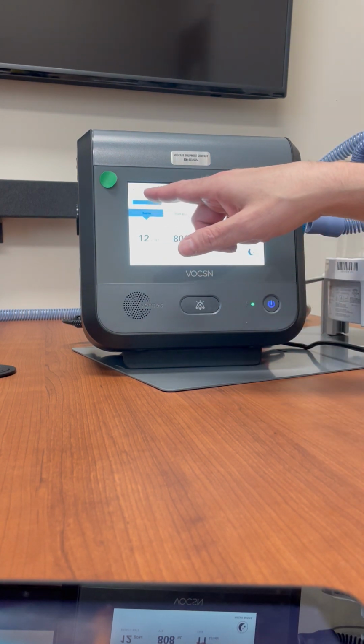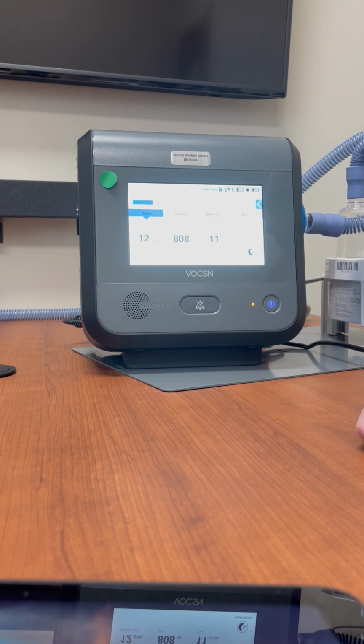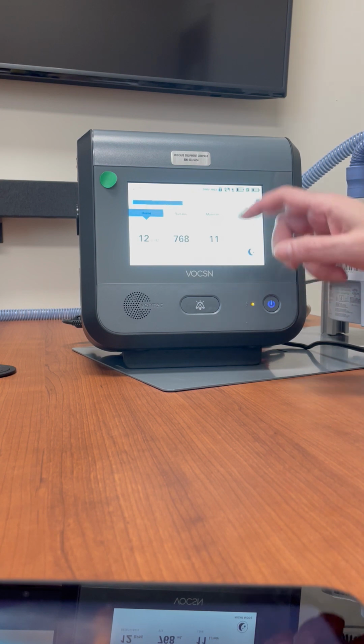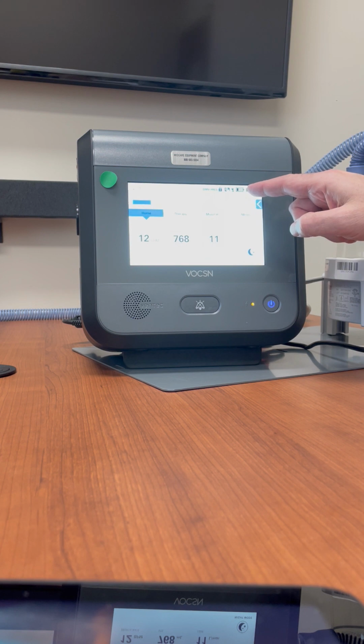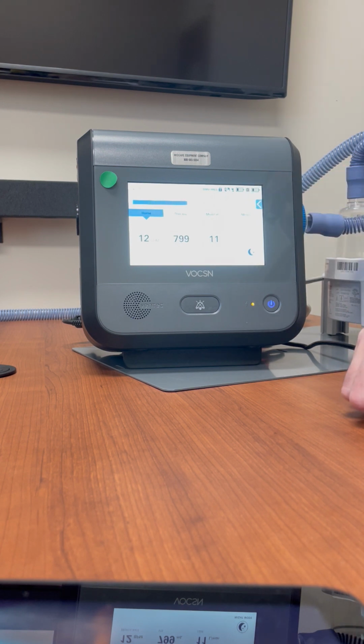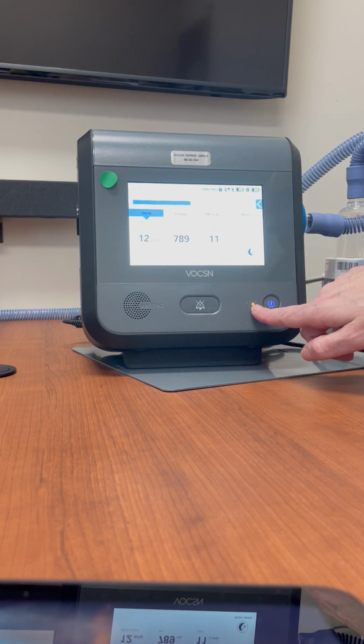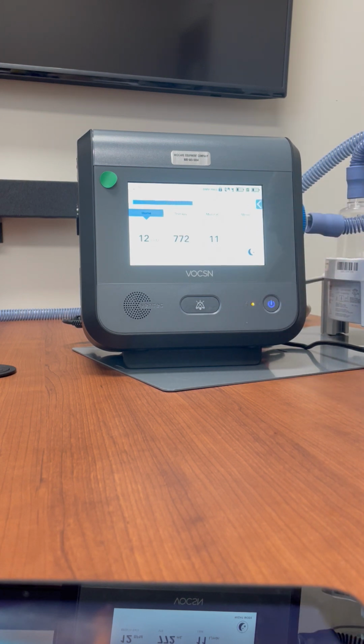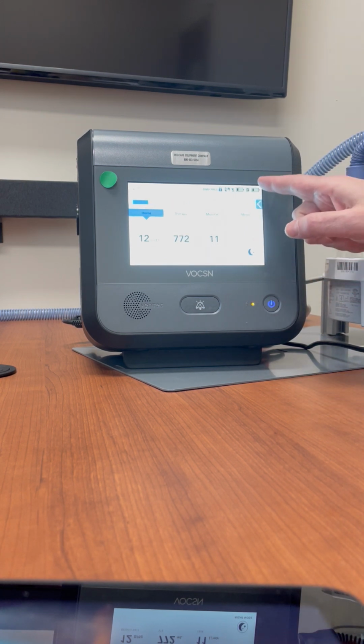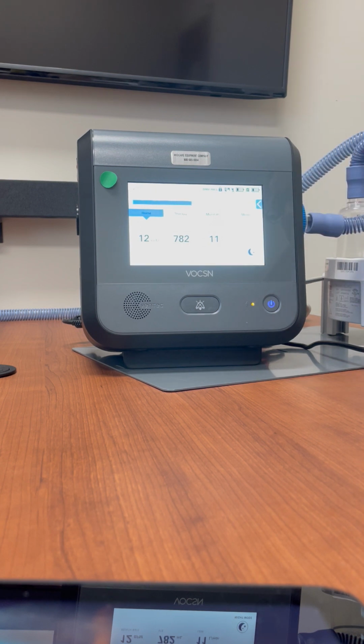On the home screen, you'll see, one, across the top, an alarm status bar. Right now, there are no alarms, but we're going to show you some here shortly. And now, just to show you, the vent on top here shows you the battery indicators. Right now, the internal battery is charging. And again, this turned back to amber to let you know you're charging. The internal battery always charges first, and once it's fully charged, the external batteries will begin to charge also. And again, next to that is a little plug icon to let you know you do have it plugged in.